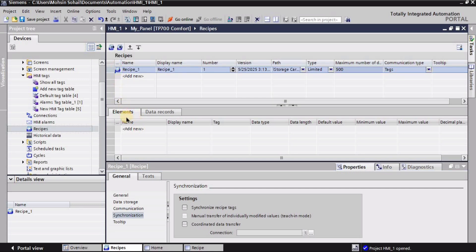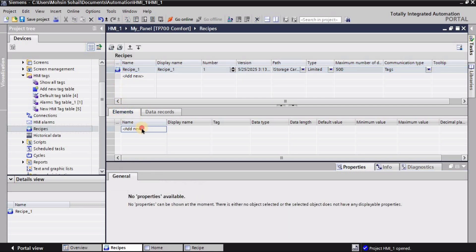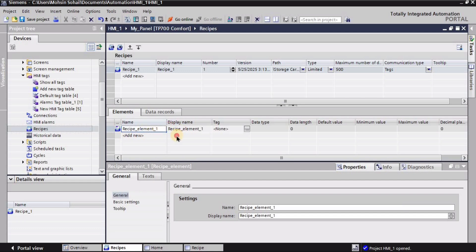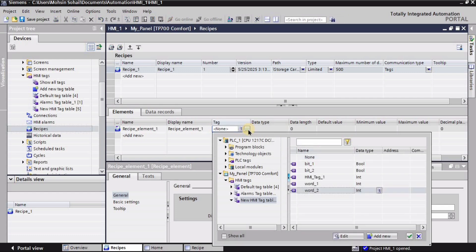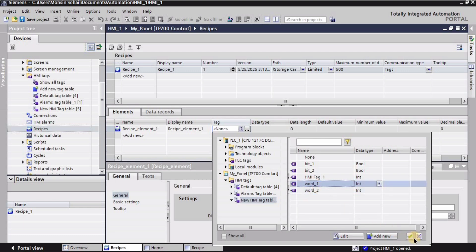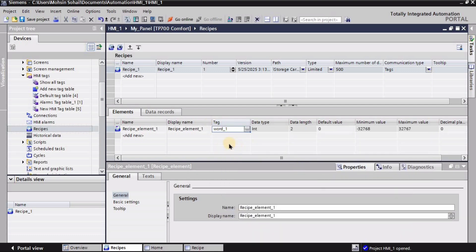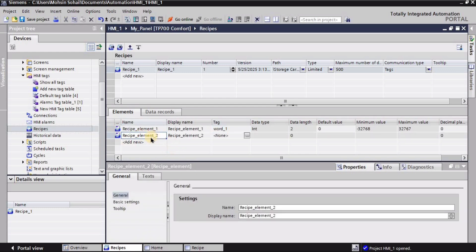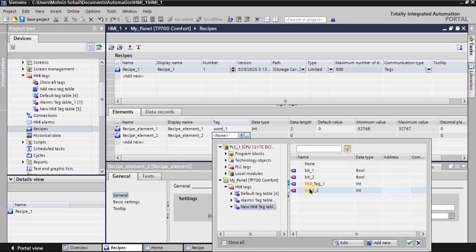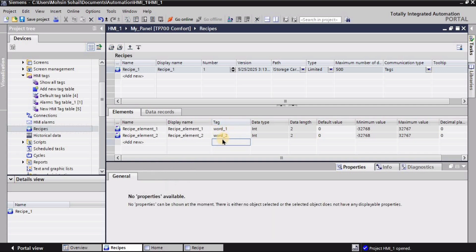And in the synchronization I want to uncheck these settings. Then I will go into the Elements. I will create two elements, going with the default name 'recipe_element_1'. For the tag I will go with the same tag given on the recipe screen: Word One, and I will check this box. Then I will create another recipe element with the default name, and for the tag I will go with Word Two that I have already added on the HMI panel screen for the recipe.